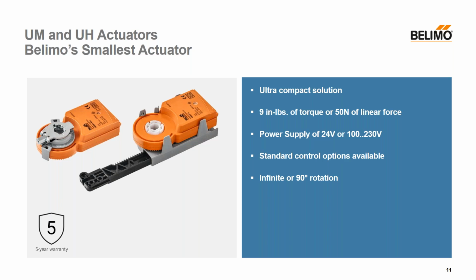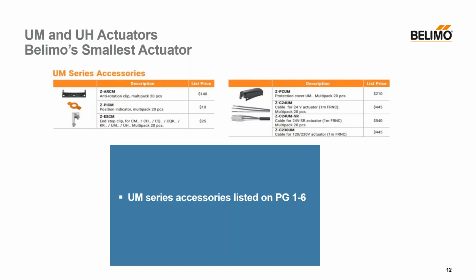We also offer a standard 3-foot cable, and the control options that are available are on-off, floating point, and 2 to 10 VDC input and position feedback. For angle of rotation, we offer infinite for open, closed, and floating, and a 90-degree rotation for the -SR model. Also on page 1-6, you will find the series accessories. Some of them include the anti-rotation clip, the position indication, and the cable options as well. These accessories come in bulk packs of quantity of 20 pieces, and the UH series we sell in single or bulk pack of 100 pieces.